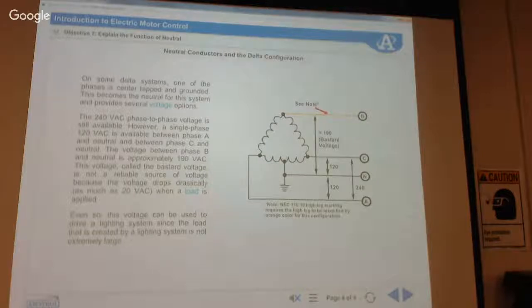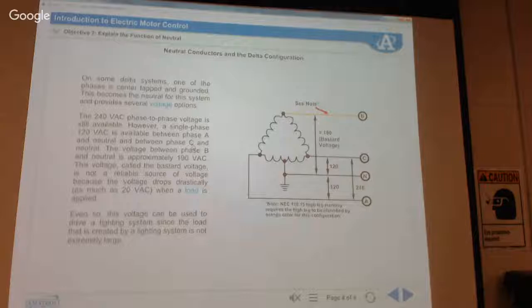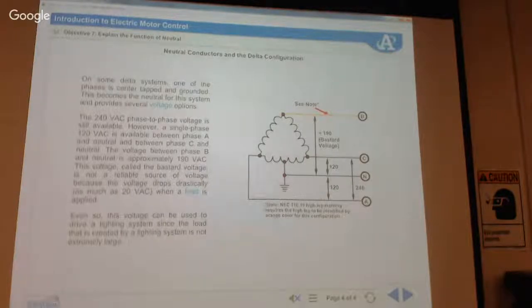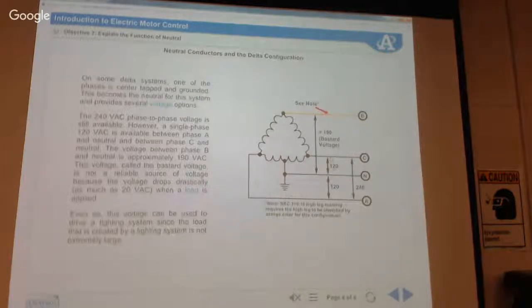So on some delta systems, one of the phases is center tapped and grounded, and this becomes the neutral for the system and provides several voltage options. The 240 volt AC phase-to-phase voltage is still available. However, a single phase 120 volt AC is available between phase A and neutral and between phase C and neutral. So if we look right here, we'll see this.